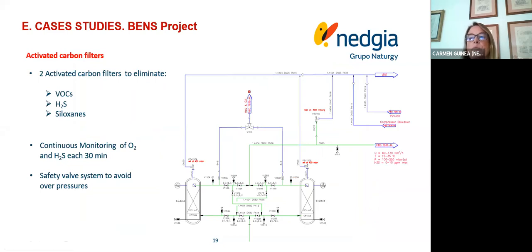The activated carbon filters eliminate the volatile organic compounds, hydrogen sulfide, and siloxane. The hydrogen sulfide is monitored every 30 minutes before, in the middle, and after the carbon filters, and the oxygen is continuously monitored. The system includes safety valves to avoid overpressure in the system.